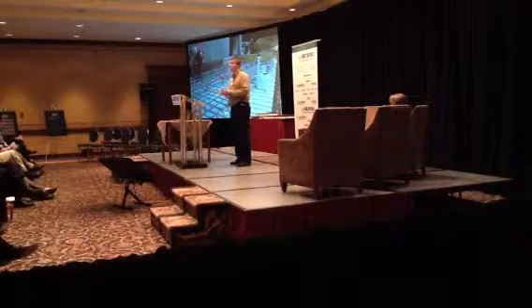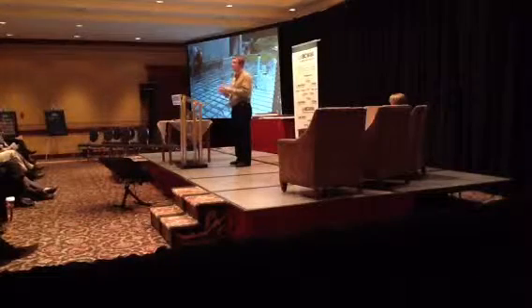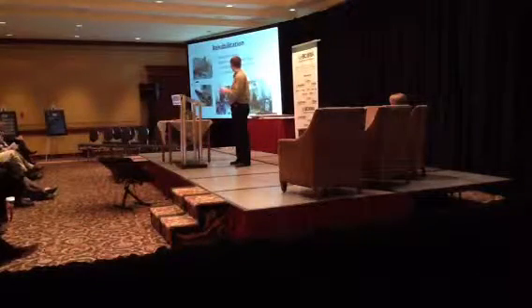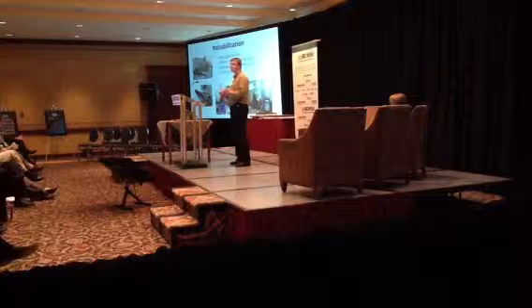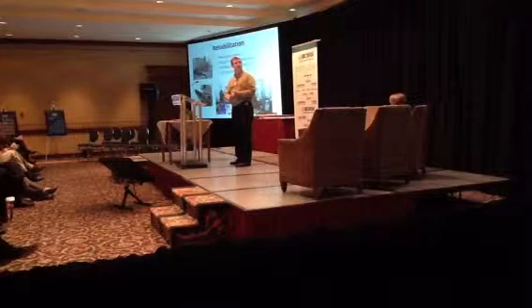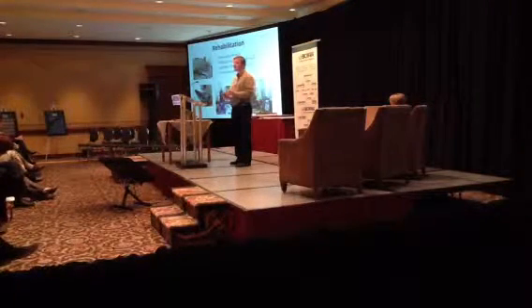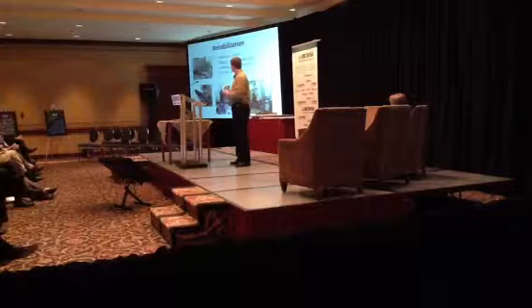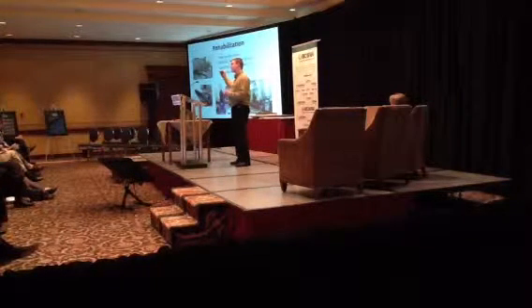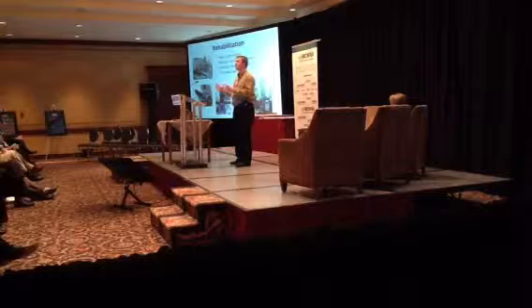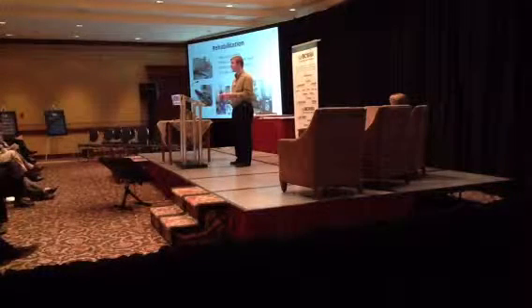In addition to the electrical upgrades, we had some very challenging mechanical upgrades to do. We replaced all of the 2400 volt motors with new 600 volt motors, and we had to do this in sequence, one pump at a time, because Simon Fraser University could only sustain a maximum of 2 hours of downtime for Kingsgate Pump Station.